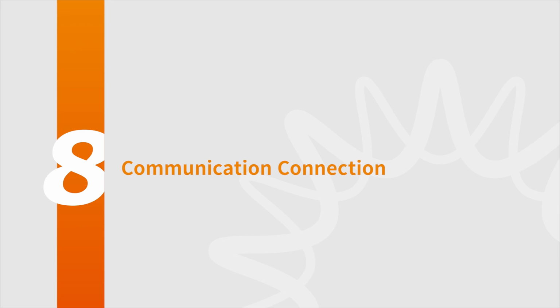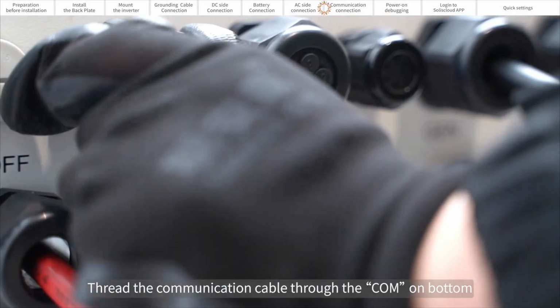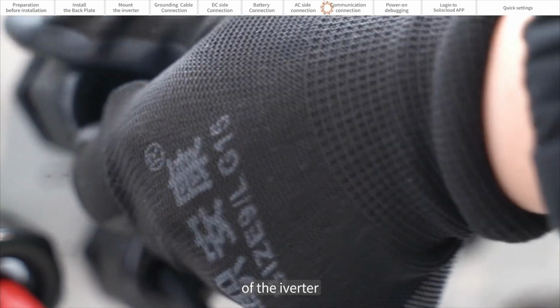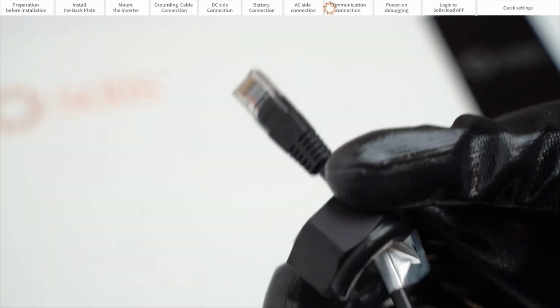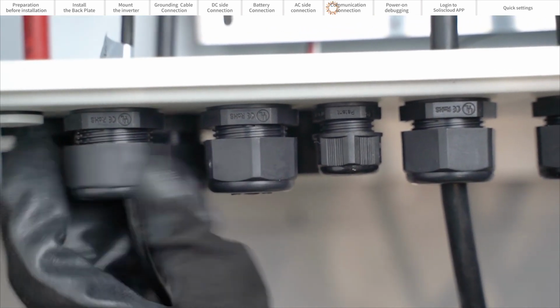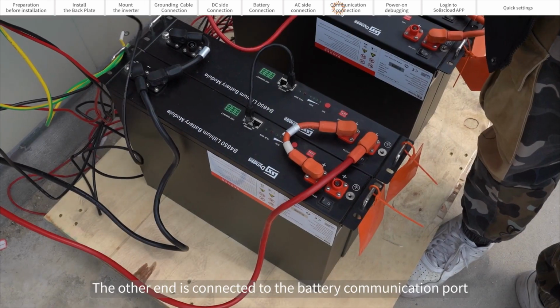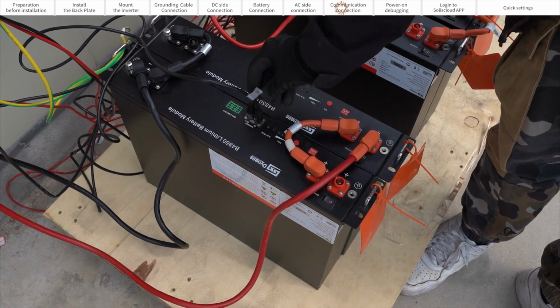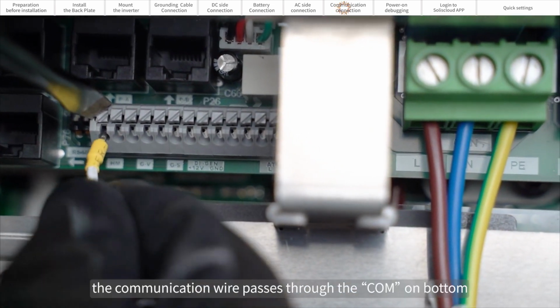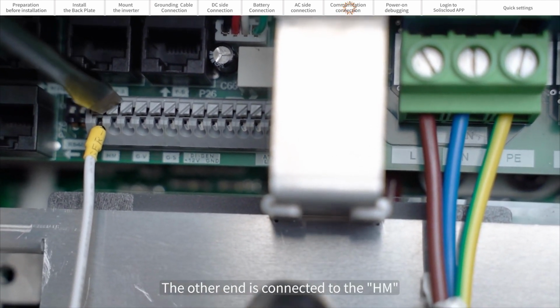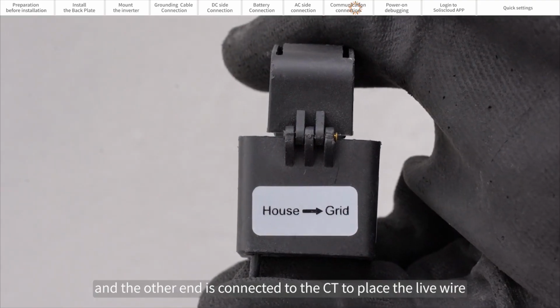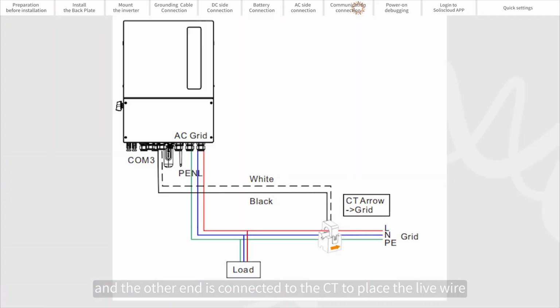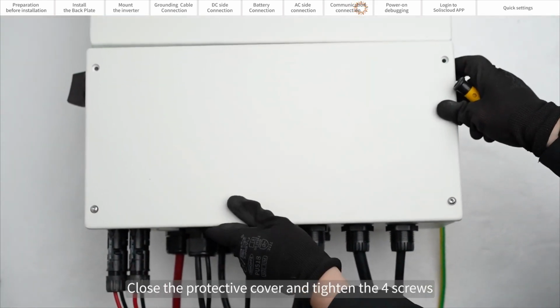Part 8. Communication connections. Thread the communication cable through the COM port on the bottom of the inverter. One end is connected to the BMS port, and the other end is connected to the battery communication port. If only CT is connected, the communication wire passes through the COM port on the bottom of the inverter. One end is connected to the meter port, and the other end is connected to the CT to place on the live wire. Close the protective cover and tighten the 4 screws.